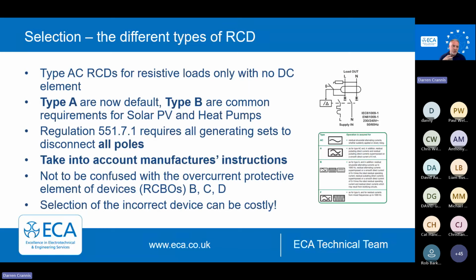But just be careful when you're choosing RCBOs that you may, for example, pick a type B RCBO as in current trip, but with a type A RCD built into it. So it can be complicated. It could be expensive. So make sure you get those right when you specify, and obviously check them at wholesalers before you install them. As we move up through the selection of RCDs, because there's a unique difference, which we'll come on to later, between the type Bs and the type Fs, they are much more expensive than your type As. And it could be to the tune of a couple of hundred pounds, £300 more expensive. So making sure we select the right ones is really important.